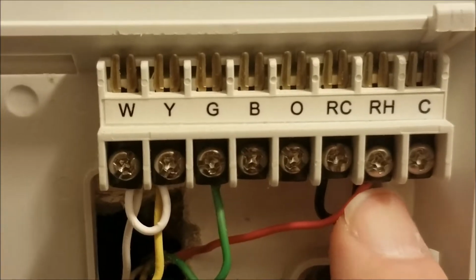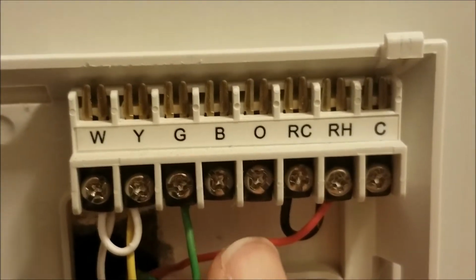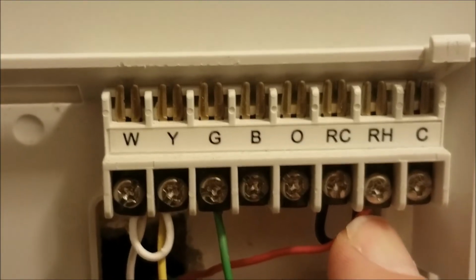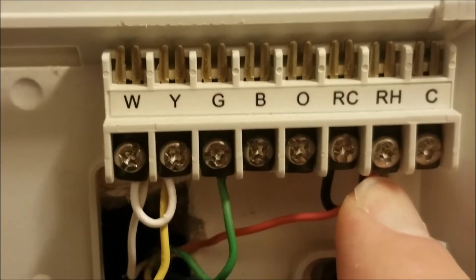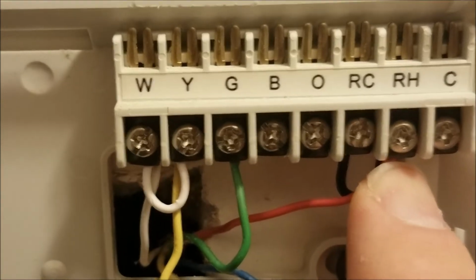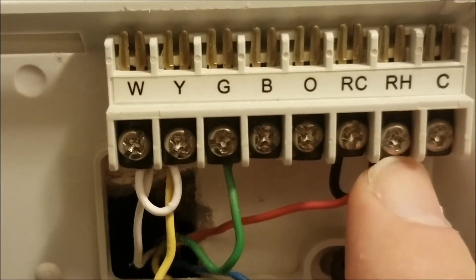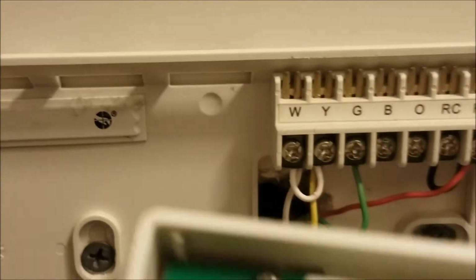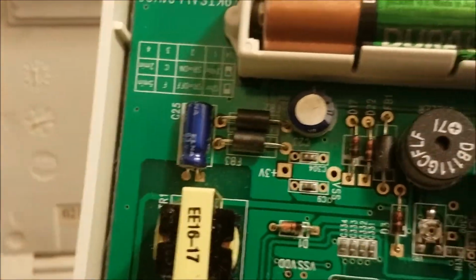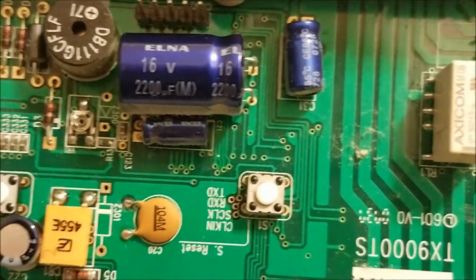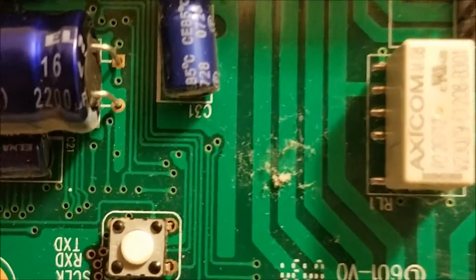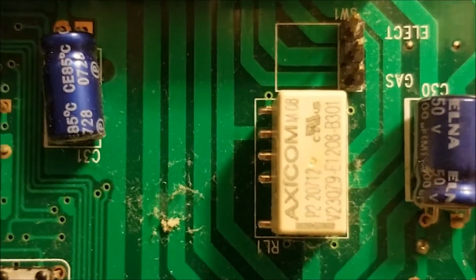This is how this works. The air handler unit will send up 24 volts into the thermostat, and when you turn the fan on by itself, inside the thermostat there's some relays. You can probably see that. Here's an older thermostat here, right there. That's probably the relay that does all the switching.